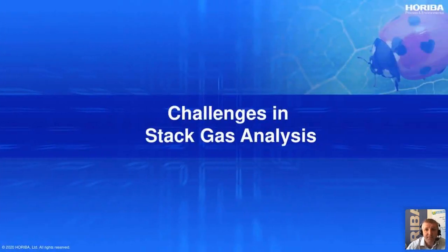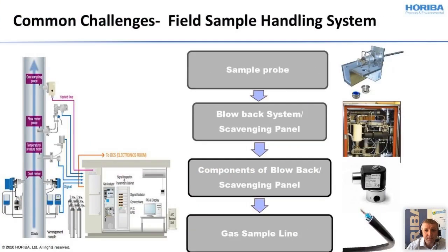So what are the challenges? The most important part of the analysis is a correctly engineered sample handling system. The analyzer model can be the best in the world, with highest accuracy, fastest analysis speed and high reliability. But when the gas is modified in a certain way by the sample handling system, the analyzer can only detect the molecules which are present in the sample gas. This ends up in the situation that the challenges of the system engineering start at the stack itself, and all of the gas parameters need to be analyzed.